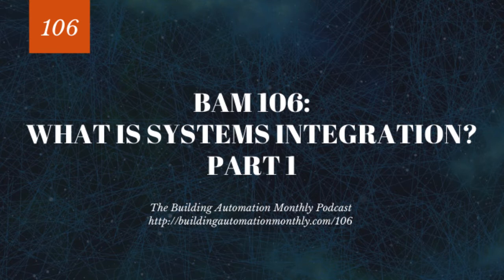I'm going to spend a lot of time on protocols, so that seems to be where a lot of folks struggle. The first concept is understanding the protocol. If you look at BACnet, if you look at LON, and you look at Modbus, they're three completely different protocols. I mean, that's obvious from the name, but I think for some folks, it's not obvious. So BACnet is a discovery protocol, and it's very much oriented around that you have a device, a BACnet device, and this device has different properties inside of it, and it has different objects.